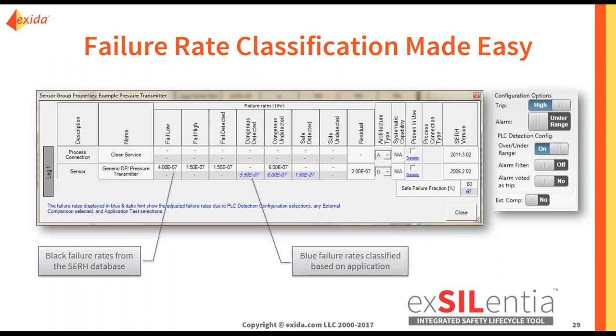Here you see a screenshot of the sensor group properties. It is showing that we have chosen a generic pressure transmitter. For that generic pressure transmitter, we have values for fail low failures, fail high failures, fail detected, and dangerous undetected failures. You can see all of those in black. Those come directly from our Safety Equipment Reliability Handbook, which is embedded in the tool. We have thousands of devices throughout the industry that you can simply choose from a drop-down list, and these failure rates are available right here.